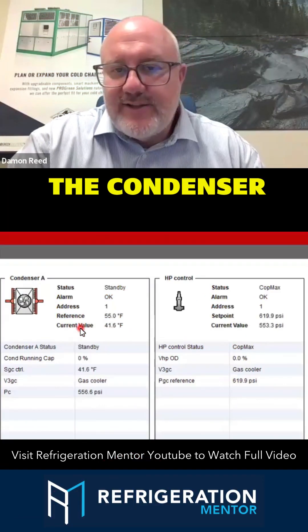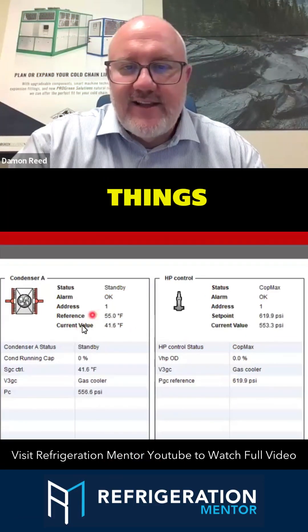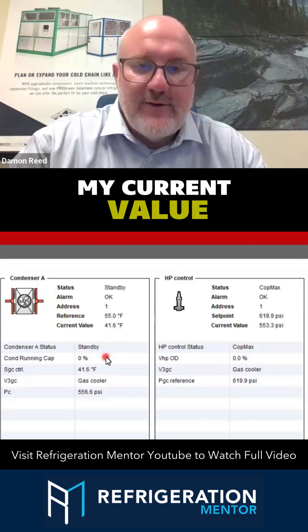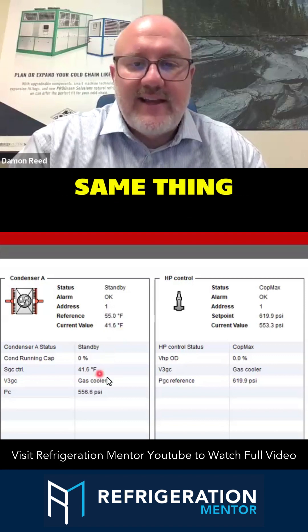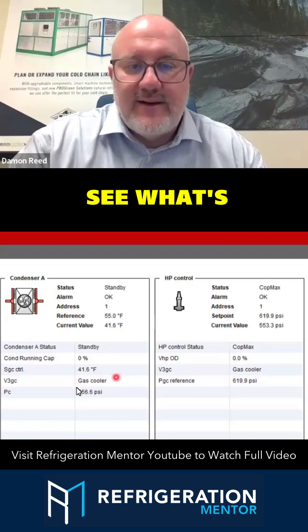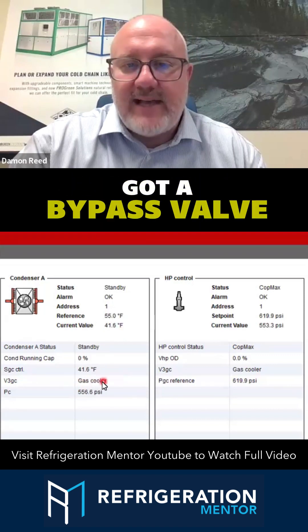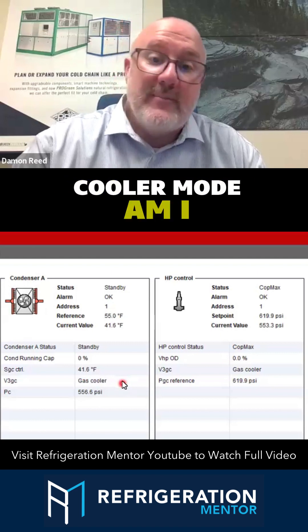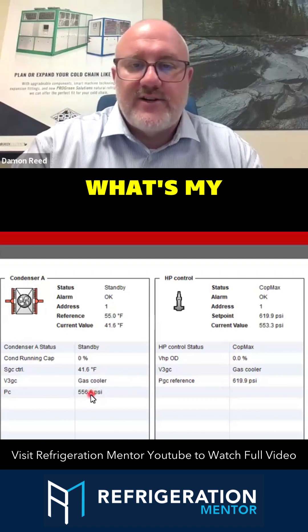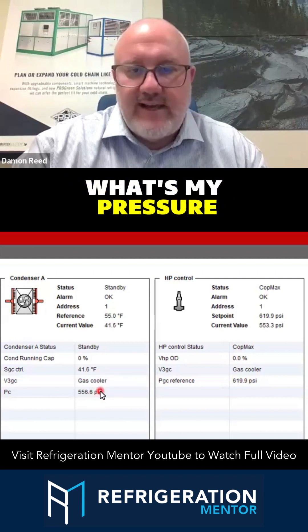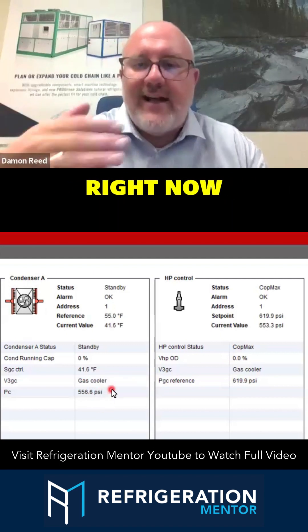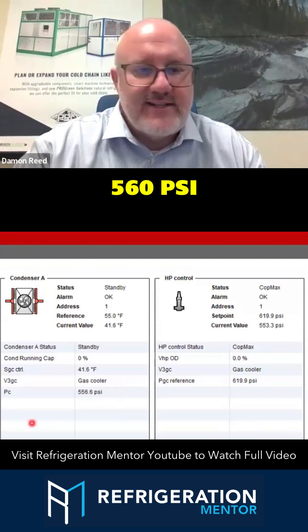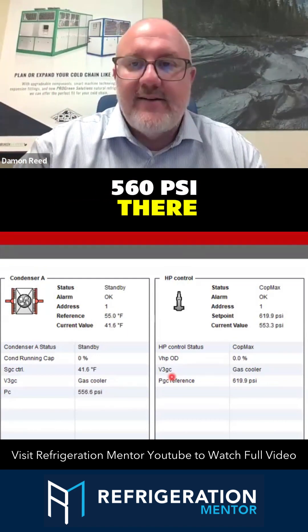Jumping over to the condenser side of things — everything's happy. I can see my reference and current value. If I've got a bypass valve, I can see am I in gas cooler mode or bypass mode, and what's my pressure. Right now I'm sitting idle, and I don't mind seeing 560 PSI there.